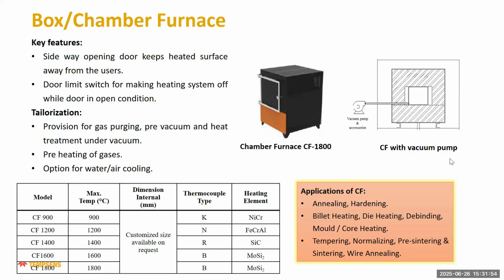We have different models, like CF 900, which can go up to 900 degrees centigrade. Sizes can be as per the requirement. Thermocouple can be K type or N type, and the heating element can be nichrome. For CF 1200, we have a temperature up to 1200 degrees centigrade. Thermocouple type will be N, and heating element will be FeCrAl. For CF 1400, we have a temperature range of 1400. Thermocouple type will be R, and heating element can be silicon carbide.